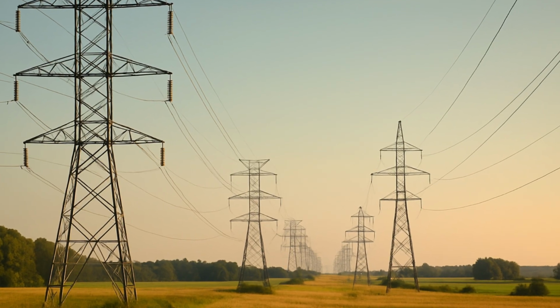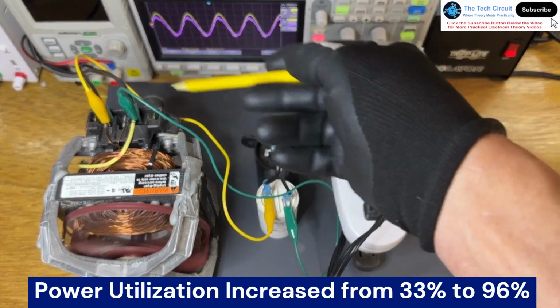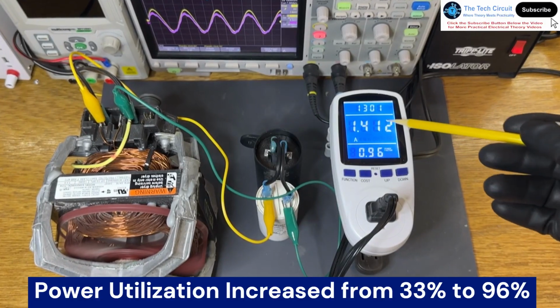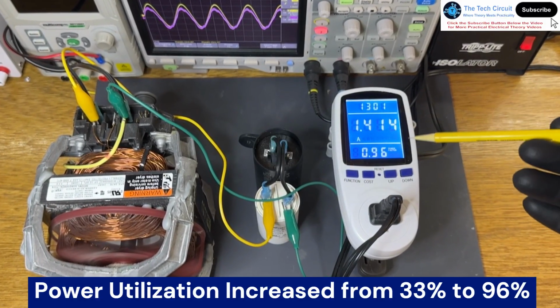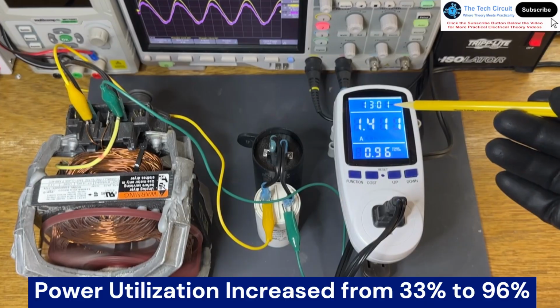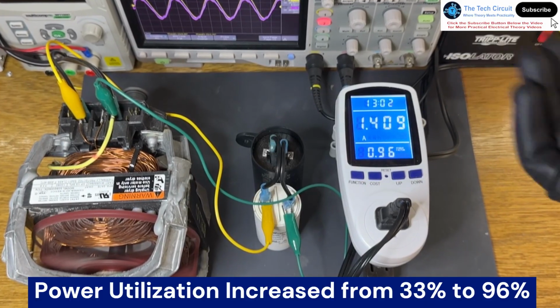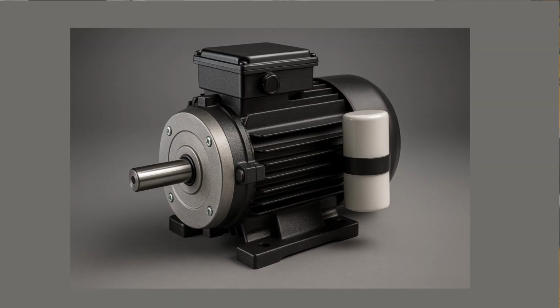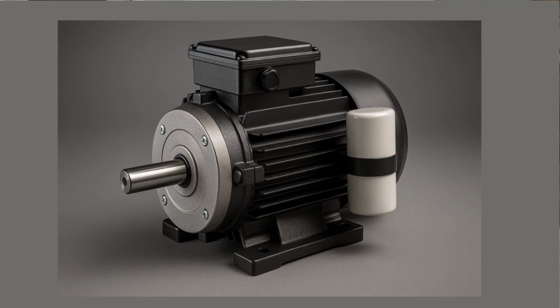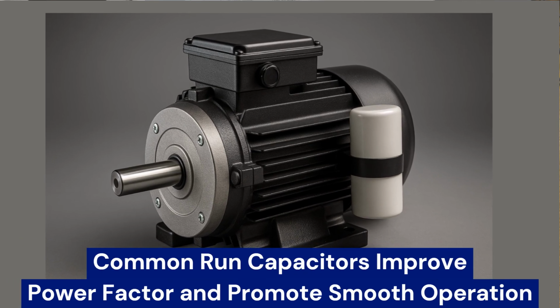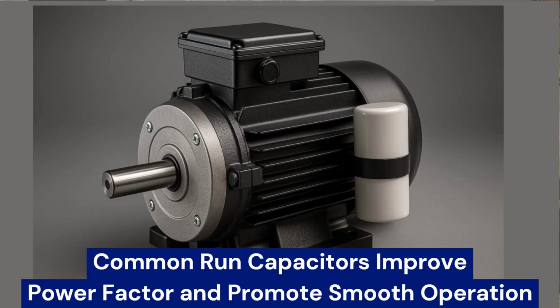By simply placing a properly sized capacitor across the motor, we've improved its power utilization from around 30-something% to around 95%. That's a huge gain in efficiency. This is one of the main reasons for run capacitors in split capacitor motors, as they improve the power factor and promote smoother, more efficient operation.